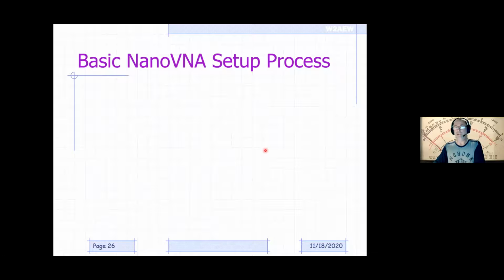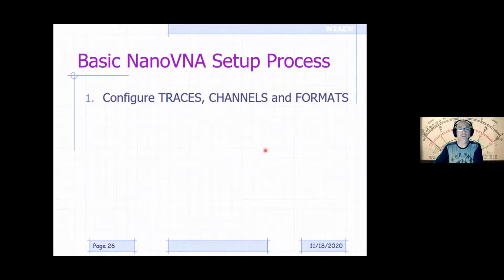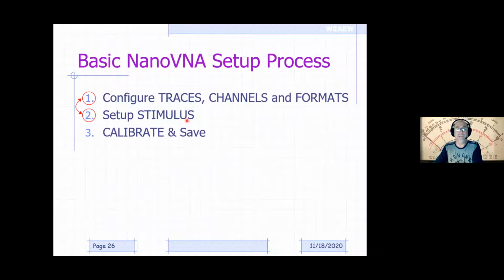So what's the basic setup process here? How do you actually go use it to do something? So the first 2 steps are configure what traces you want turned on, what channels you want those traces attached to, and what formats you want those traces to be displayed in. And you want to set up the stimulus, the start and stop frequency, or the center and span. Those 2 can be done in either order. It doesn't really matter which one you start with, but those 2 things you want to set up first, and then go ahead and run the user calibration, and then save it. It really doesn't matter, again, what order you do this.